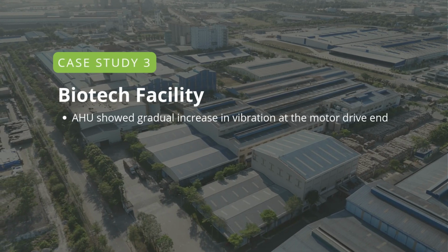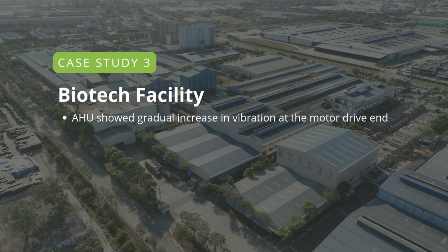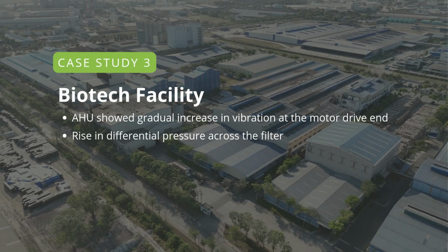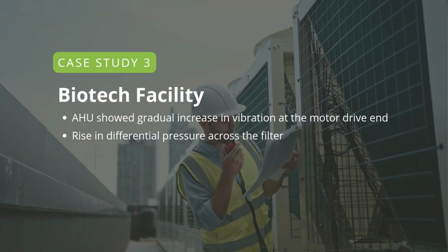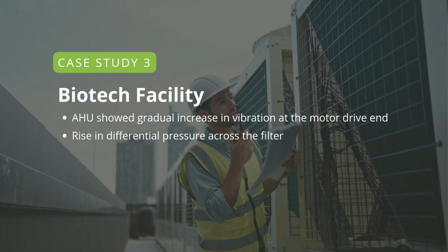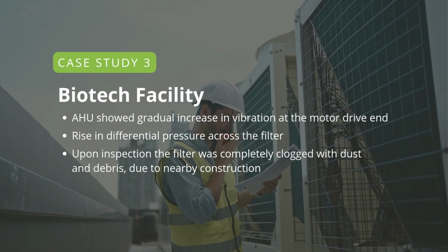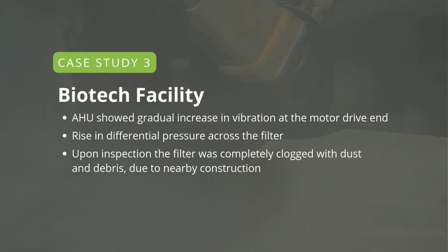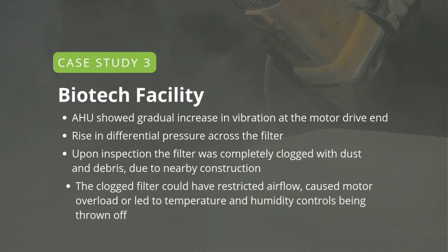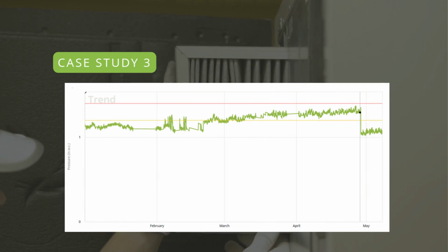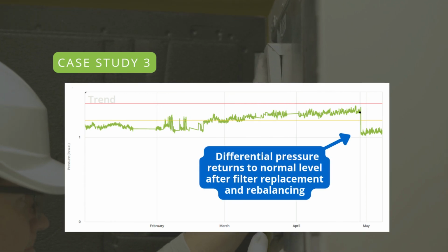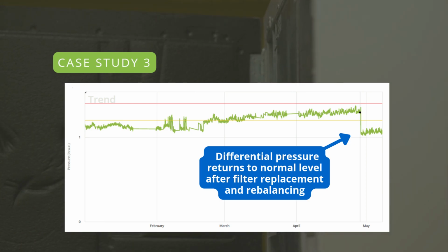Sometimes, the root cause of a machine health issue isn't mechanical, and that's where multiple parameters come in handy. In this case, an AHU began showing a gradual increase in vibration at the motor drive end. At the same time, the system also saw a rise in differential pressure across the filter. These two trends together triggered a maintenance notification, and upon inspection, the team found that the filter was completely clogged with dust and debris due to nearby construction, which caused excess dust buildup. If left unchecked, the clogged filter could have restricted airflow, caused motor overload, or led to temperature and humidity controls being thrown off. But with early detection, the team was able to change the filter, rebalance the belts, and bring the system back into optimal range, avoiding both equipment damage and product risk.